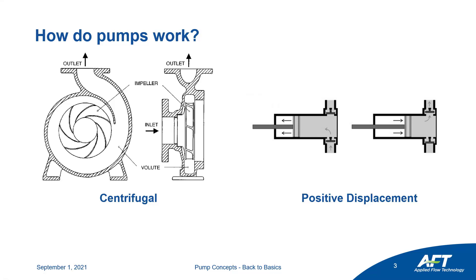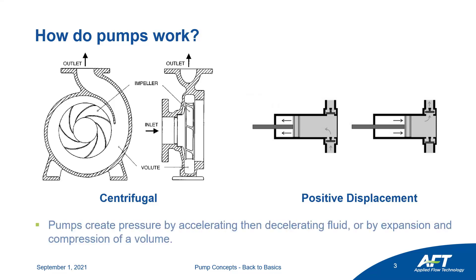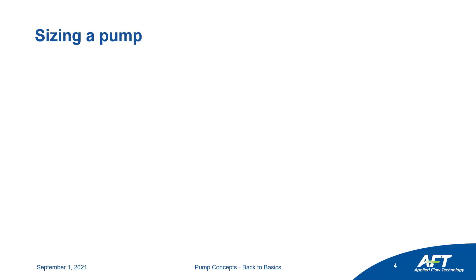Starting from the barest foundation: how do pumps create pressure? A centrifugal pump creates pressure by accelerating the fluid with the impeller, then decelerating it with the wall. A positive displacement pump sucks fluid in and then by compressing it creates the high pressure necessary to overcome the check valve. A lot of the concepts in this webinar are going to focus on centrifugal pumps because those are the majority of pumps in systems.